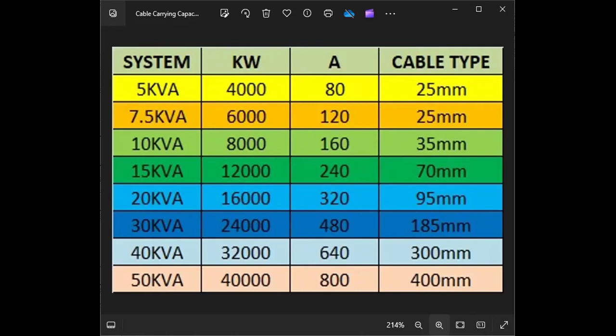The same thing applies to the next one. We're talking about a 7.5 kVA, which is 6,000 watts, and the maximum current is 120 amps. So a 25 mm should be able to accommodate that. And the same thing applies for various capacities. We have 5, 7.5, 10, 15, up to 50 kVA, with the corresponding amount of current they should deliver, and the corresponding cable sizes you should use for such connections. So I don't know if this is very clear.